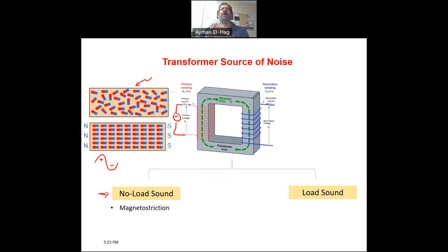This will lead to some elongations and contractions of the transformer core and that will cause some vibration and hence it would cause the sound that we hear or part of the humming sound coming from the transformer. So this type or this source of noise is 24-7 because it is linked to the voltage. The transformer is always energized. Always you will have the full flux in the transformer.